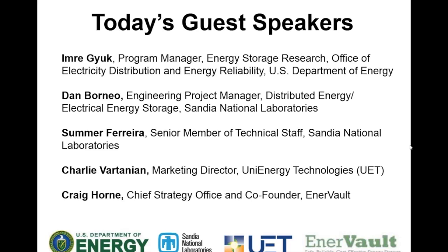Okay. And to share a single data point, I just wanted to share the 1,000 per kilowatt hour. I'll just share UET. That's indicative of a total installed cost: balance of plant, site improvements and equipment. Obviously, the battery itself is south of that. But what's good for most flow batteries, there's good line of sight on cost as scale comes up. They're just simple procurement efficiencies that drive down the cost. So I do want to qualify that there are no breakthroughs in science needed for the most developed forms of flow batteries. Several of us are on the way to a cost reduction curve based on just simple industrial and commercial practices.